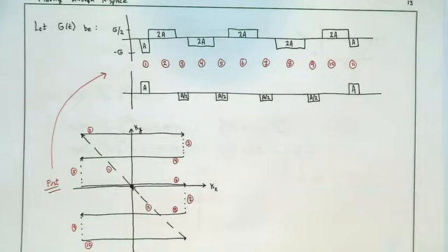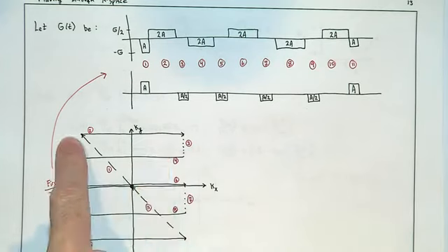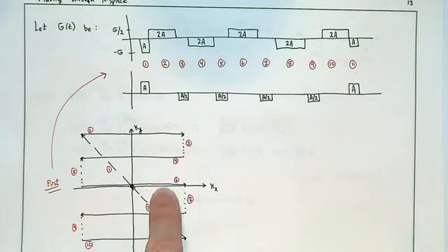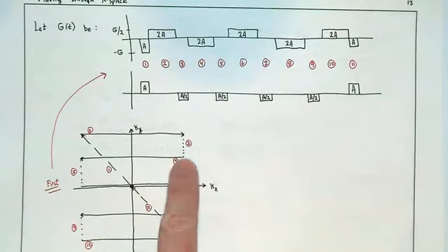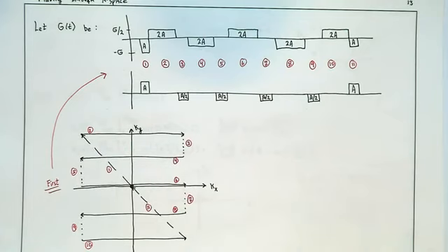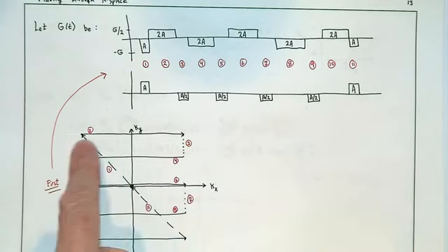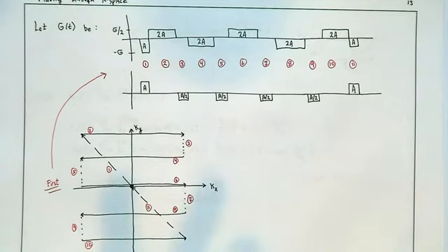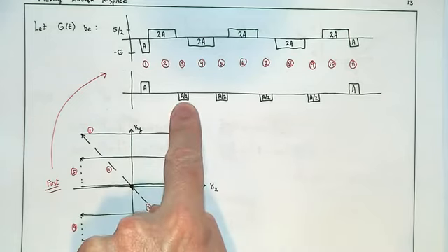When it comes to actually designing sequences, which requires the most gradient area, getting to this line of k-space or getting this line of k-space? Or maybe it's easier to compare. Do I need more gradient area to get to this line or to this line? A or B? B, right? I need more gradient area. The gradient has to be stronger or on for longer to get out to this line here. So usually you design your sequence for the k line that's farthest out because that requires the most area. And because of hardware limits or something else, that will dictate how long it takes to apply that gradient.